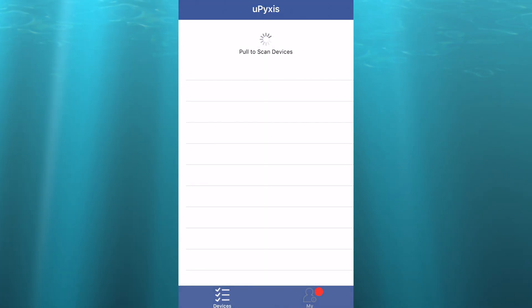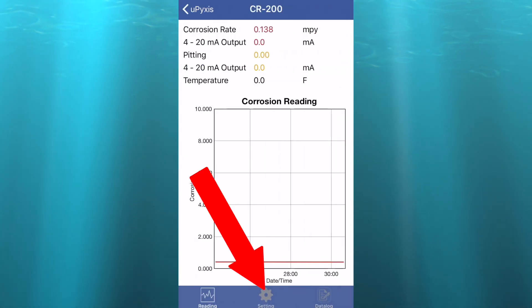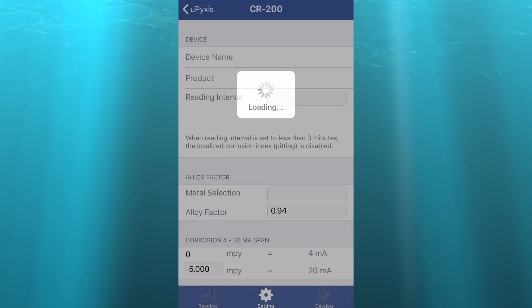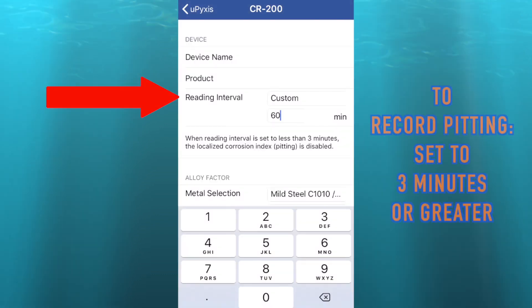Now in the uPyxis app, select the CR200 and select the settings tab. Here you can customize the device name, water treatment product, and the reading interval. Please note that in order to record localized pitting data, the reading interval must be set at three minutes or greater.